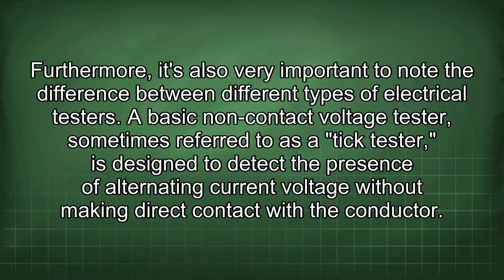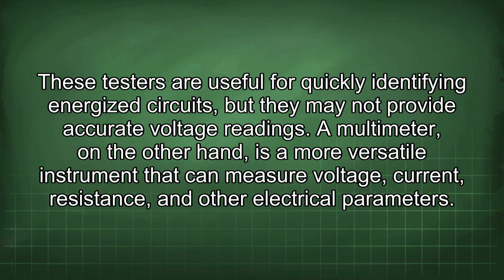Furthermore, it's also very important to note the difference between different types of electrical testers. A basic non-contact voltage tester, sometimes referred to as a tick tester, is designed to detect the presence of alternating current voltage without making direct contact with the conductor. These testers are useful for quickly identifying energized circuits, but they may not provide accurate voltage readings.